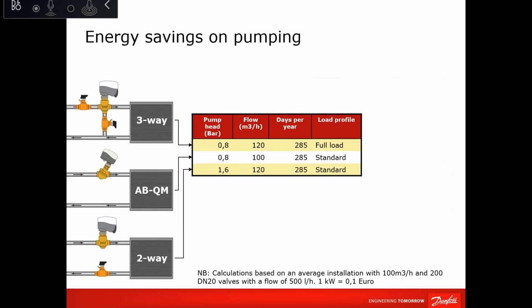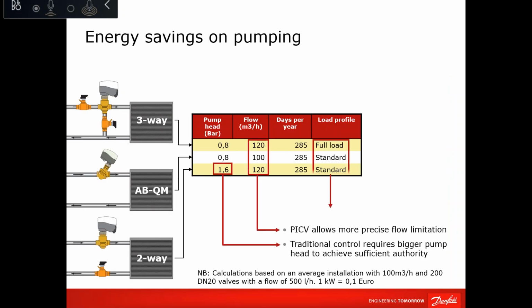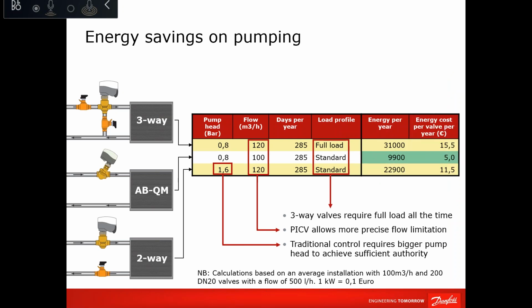So how does it save energy? If we take the example of the pumping, this is a comparison between a three-way, two-way, and the ABQM, PICV. The three-way is simple. It requires full load, full head. So it's the most energy consumer in euro per valve per year. Now, if we take the example of a two-way valve, you need a higher flow and a higher head, which means to achieve the same comfort level, you need to pump more at a higher head.